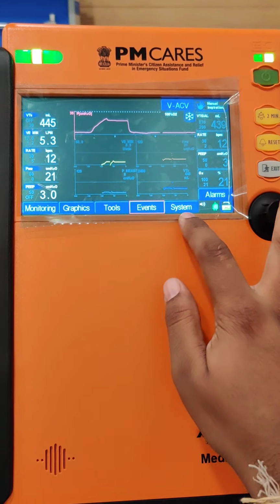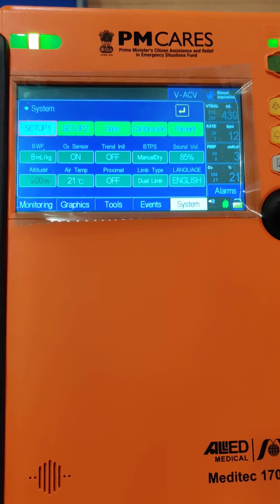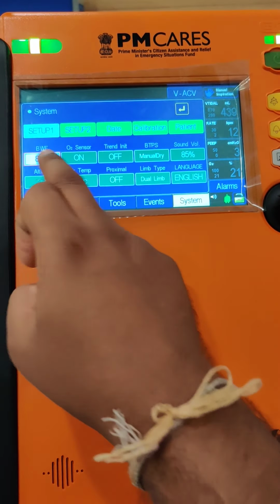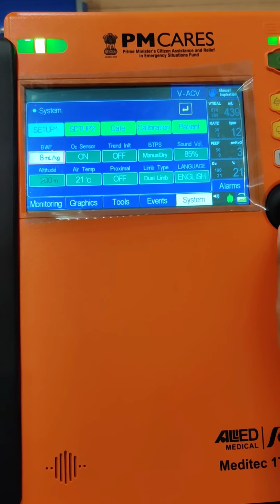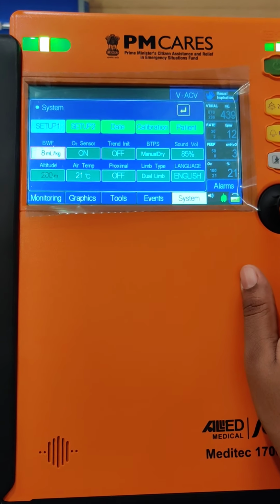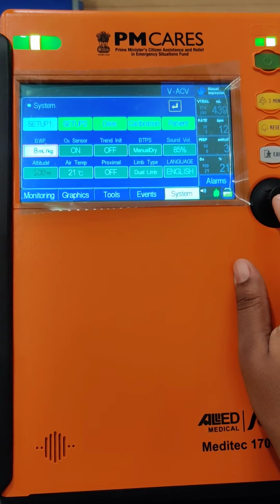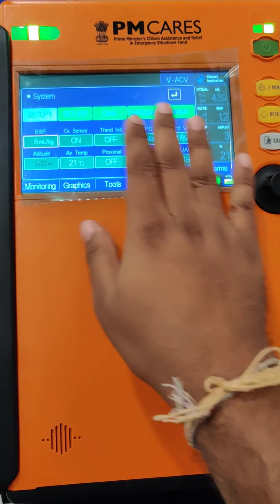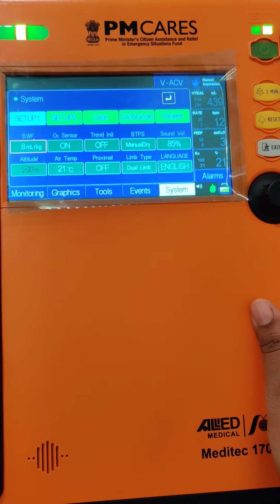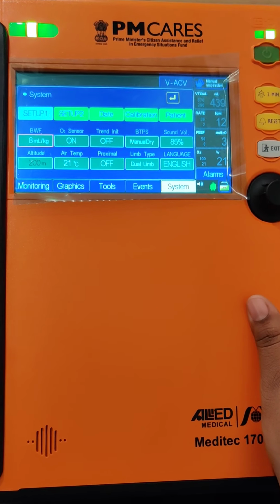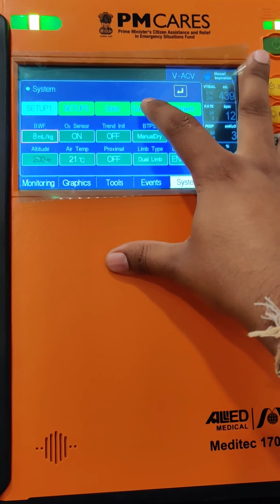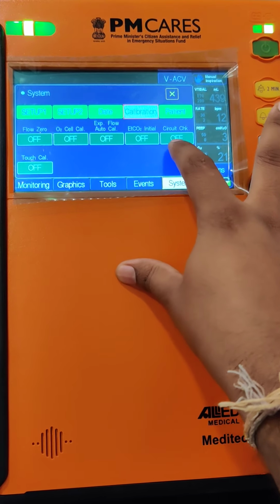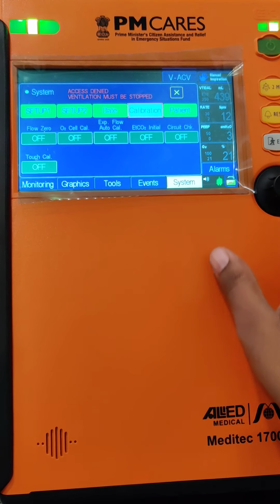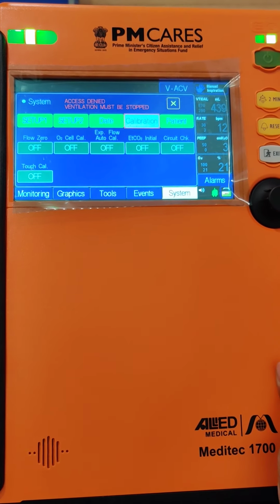Now the next key is the system key. Here you can only change the body weight function, that is 8 ml per kg or 10 ml per kg, according to your requirement. By default the ventilator is set at 8 ml per kg. The rest of the things are for service engineers for servicing. The only thing you can carry out in this is the leak test circuit check, and that has to be done in the standby mode, which I will be demonstrating at the end of the video.